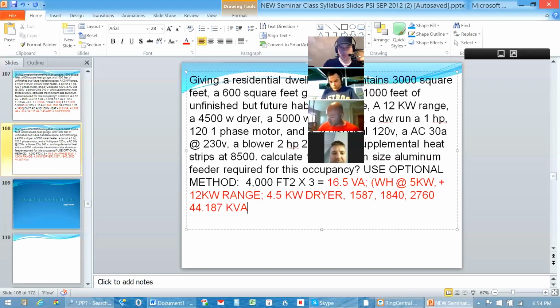What was the 2760? The 2760 was that blower motor, which I'm including as a motor load under section 4, not as a part of the heating, because the blower motor is going to be a motor load and it's going to operate all the time anyway, so it's not really part of the air conditioning when it comes to section C. Oh, okay. If they ever separate a blower motor like that on you on the air conditioning, you want to include it as just a regular motor load and then just forget about what it does. It's just a motor. But we don't increase it times 125%. We're just taking it at 100% of its rating.